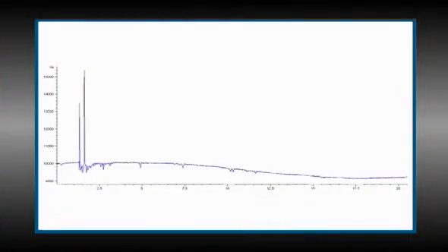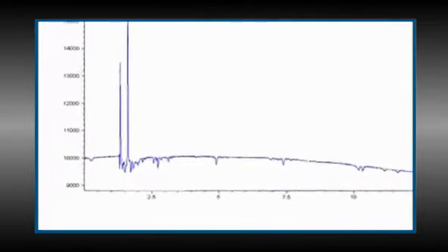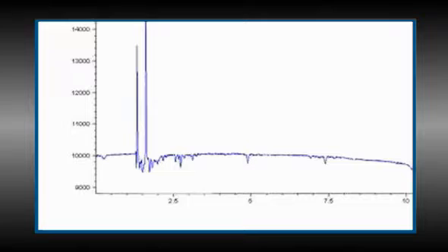Yes, they do. Well, let's talk about excessive baseline noise. As we use the GC, especially if we're working with dirty samples, we may see the baseline getting noisier and noisier over time. Biological samples, samples with high molecular weight components, fish oil, petroleum samples, etc., can all have things in them that we're really not interested in looking at, but we have to deal with anyway.